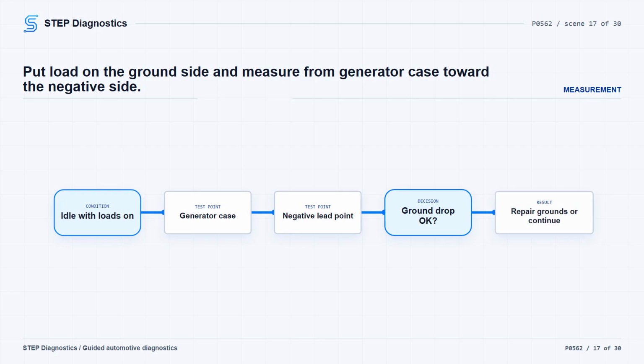With the engine still running at idle, headlamps on, and the heater blower on high, measure voltage drop between the generator case and the specified negative lead location. The voltage drop should be less than 0.5 volt. If it is not, inspect and repair the engine ground, generator ground, or battery ground for corrosion. If the ground side passes, continue to command versus response testing.